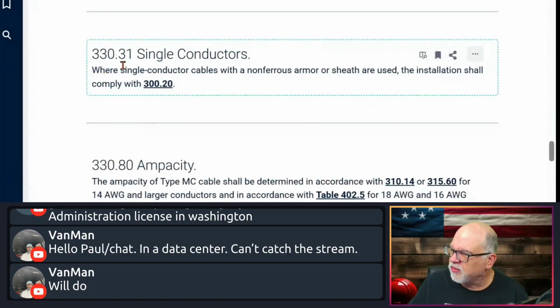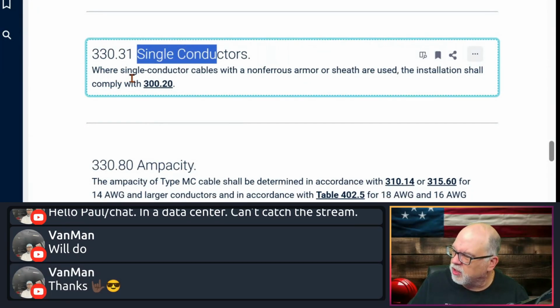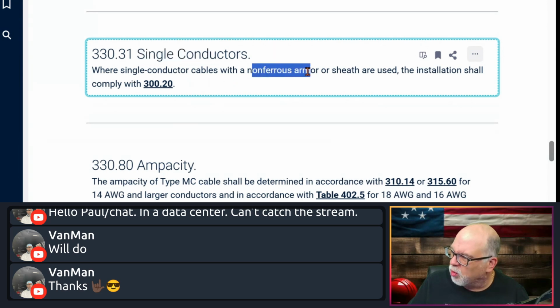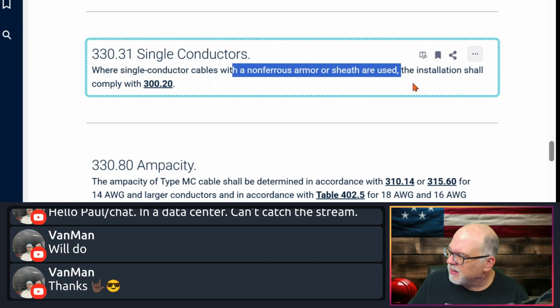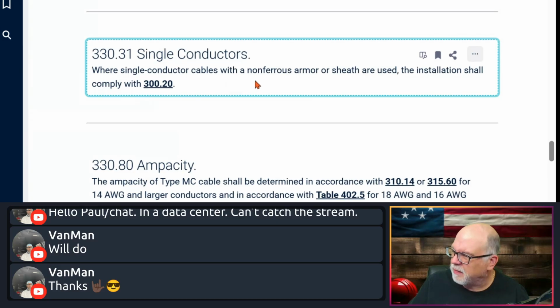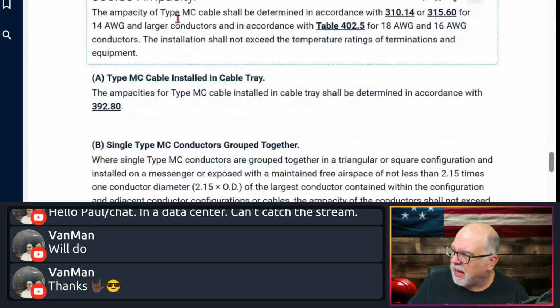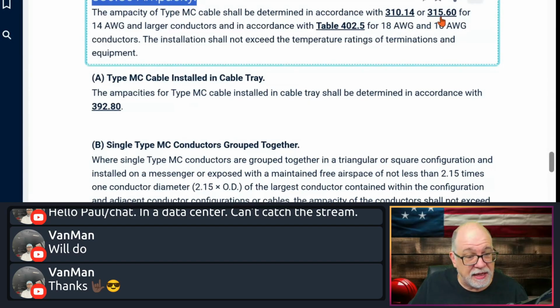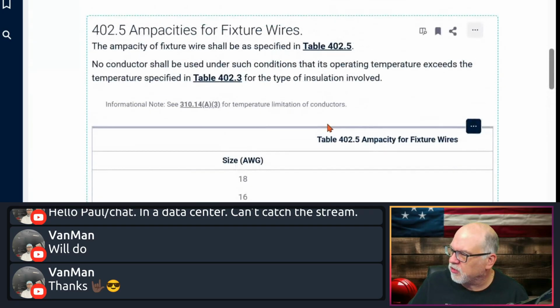All right, 330.31, single conductors. Where single conductor cables with a non-ferrous armor or sheathing are used, the installation shall comply with 300.20. Keep in mind that application. Ampacity: the ampacity of type MC cable shall be determined in accordance with 310.14, or 315 if you're using it for a medium voltage application or over 2000 volt application, for 14 and larger conductors, and in accordance with table 402.5 for 18 and 16. That's smaller conductors. If you're not familiar with 402.5, it's fixture wire ampacities.